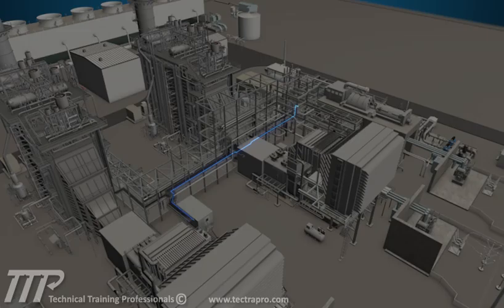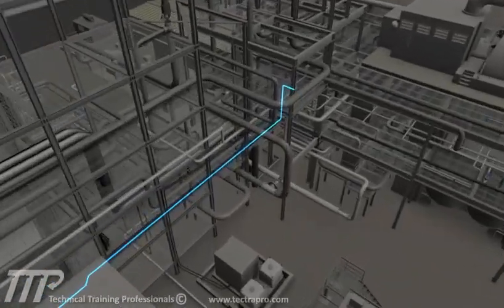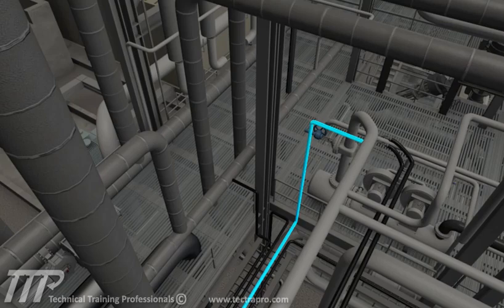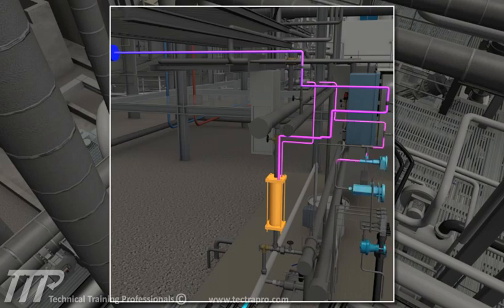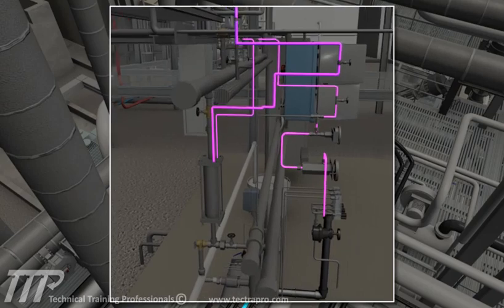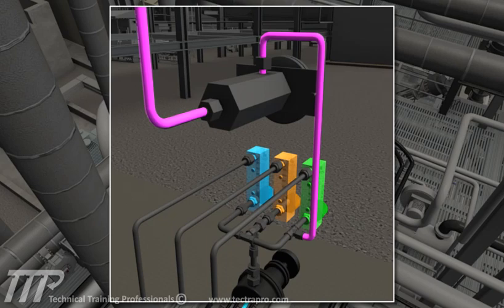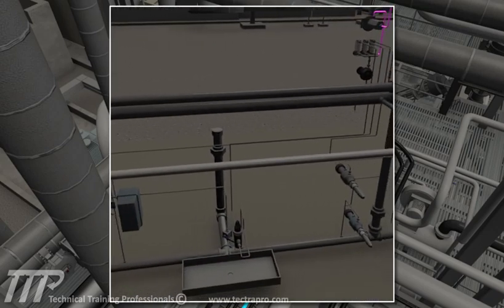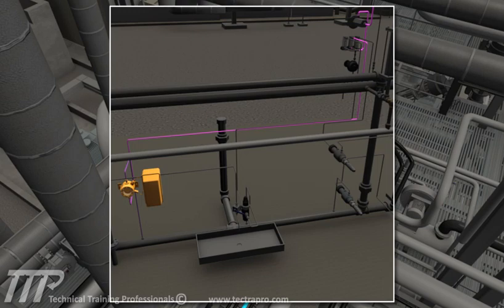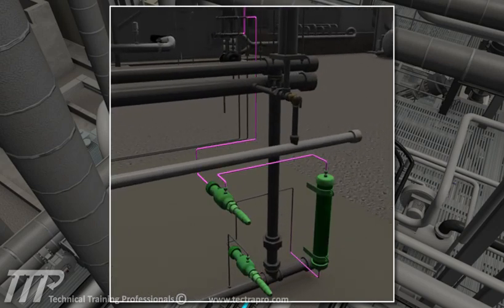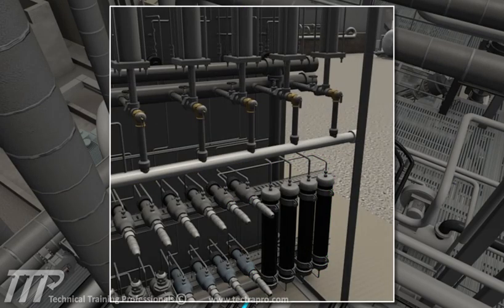Sample point 2 is the condensate discharge downstream of the chemical injection point, to monitor the condition of the water before delivery to the heat recovery steam generators. At the sample panel, the condensate is cooled and its pressure is adjusted. From here, the sample is divided into three streams, each with a different flow rate. One stream flows to the pH analyzer, the second to the dissolved oxygen analyzer, and the final stream to the cation conductivity and specific conductivity analyzers. Provisions for manual sampling are available to further analyze the conditions of the water.